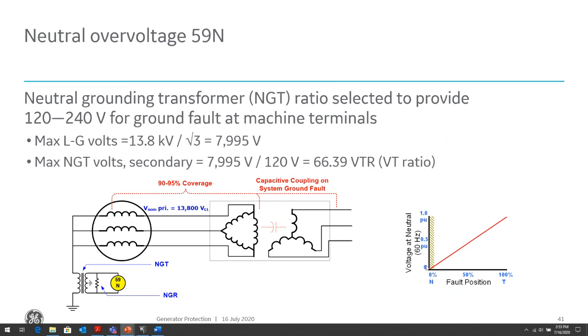So for this type of protection, when the fault is close to the neutral of the generator, we won't be able to see that ground fault current. That's why this provides about 90 to 95% coverage, because when the fault gets close to the neutral, the voltage is basically close to zero, and we can't discriminate because of the sensitivity of the relay and of the transformer that's reading the voltage, and the inaccuracies in that equipment. We can't detect faults close to the neutral, or about 0 to 5% in the low winding area.